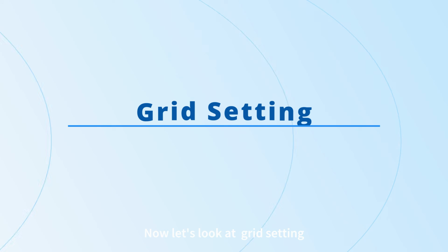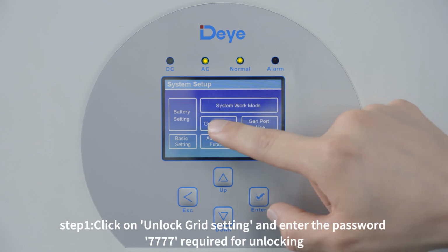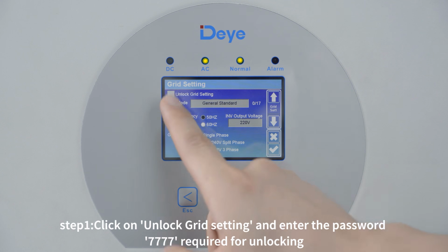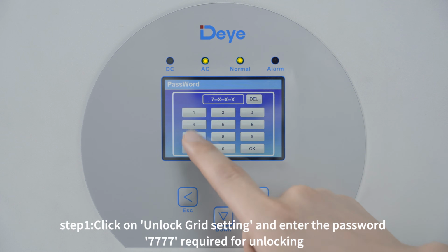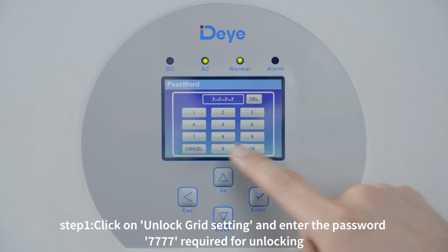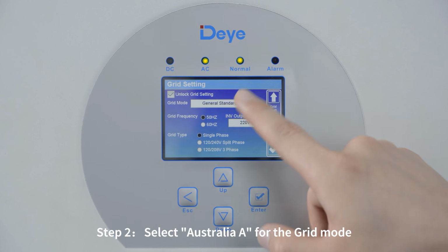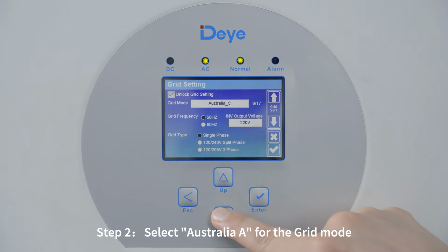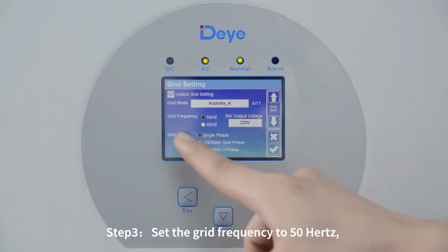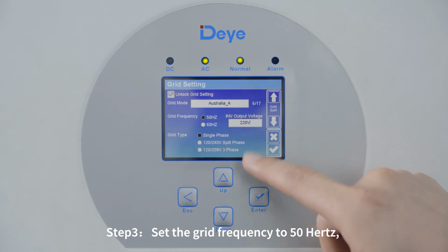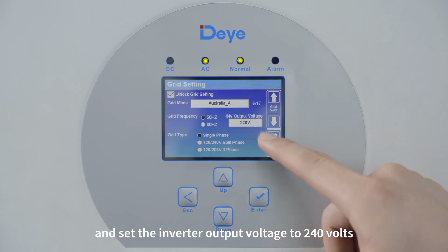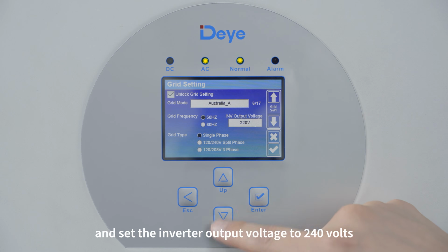Now let's look at grid setting. Step 1. Click on Unlock Grid Setting and enter the password. 7777 is required for unlocking. Step 2. Select Australia A for the grid mode. Step 3. Set the grid frequency to 50 Hz, and set the inverter output voltage to 240 volts.